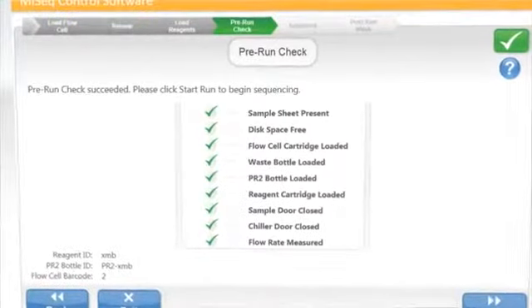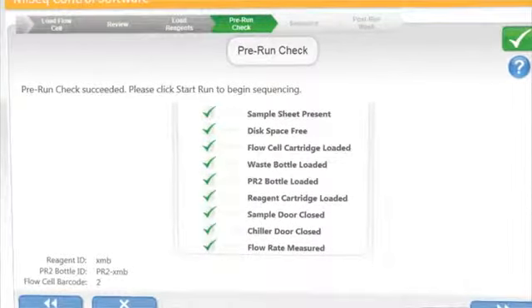It'll make sure that all of the fluidics are working and every other aspect of the system is functioning as it should be. It'll even tell you if you try to do a type of application that's not suited to the reagents that are loaded, that you need to either change the reagents or change the program. It's very clever and designed to make your life as a researcher very easy.